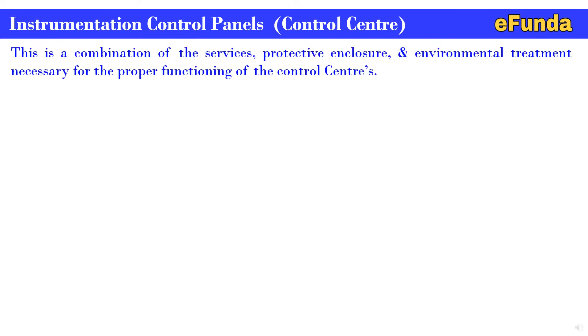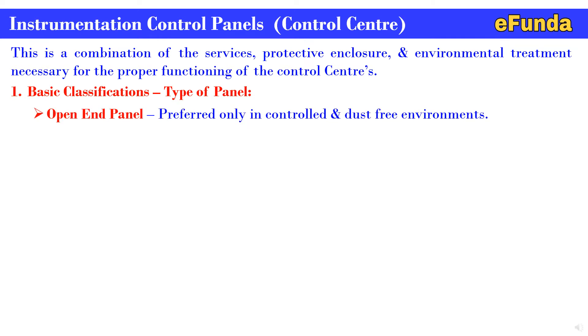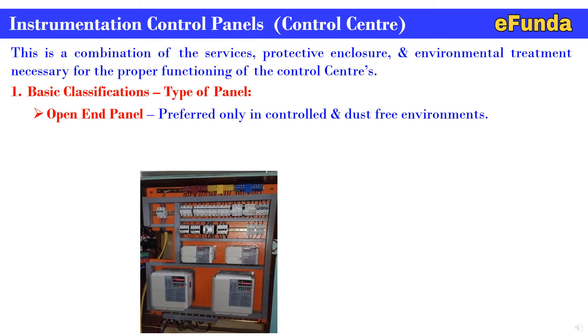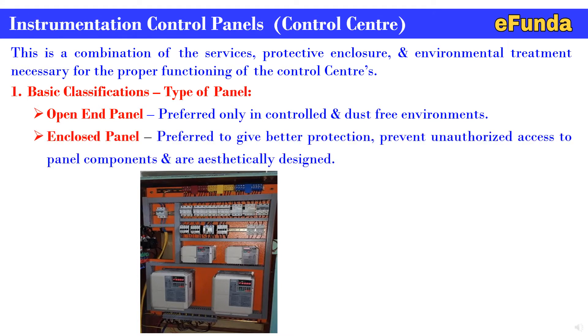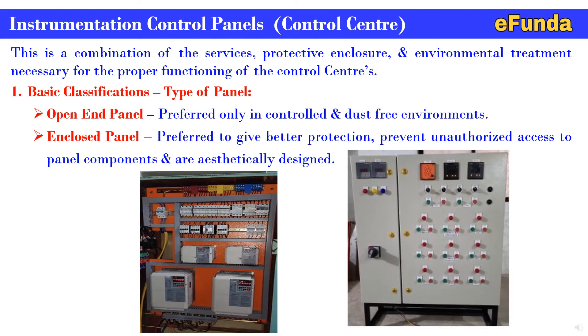Continuing with instrumentation control panels: this is a combination of services, protective enclosure, and environmental treatment necessary for the proper functioning of the control center. Now we will see the various types of control panels. First basic classification — type of panel: first, open end panel, preferred only in a controlled and dust-free environment. Second, enclosed panel, preferred to give better protection, prevent unauthorized access to panel components, and aesthetically designed. All components are assembled inside the panel and enclosed by a door, with all monitoring controls and push buttons indicated on the front.